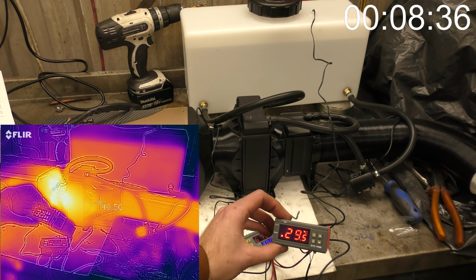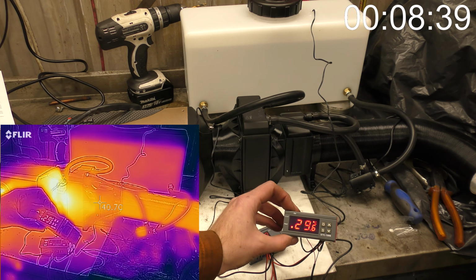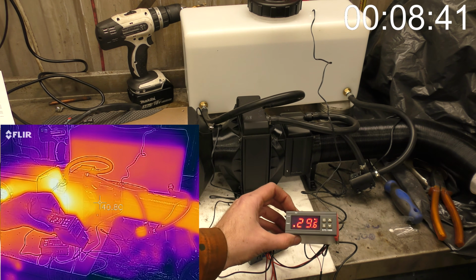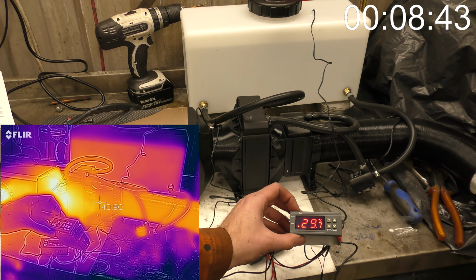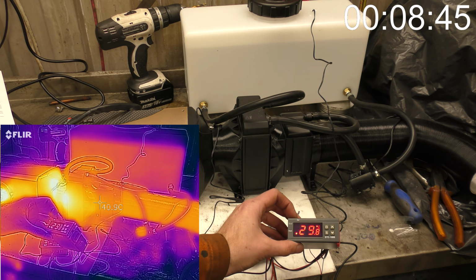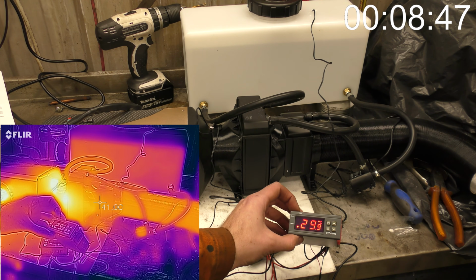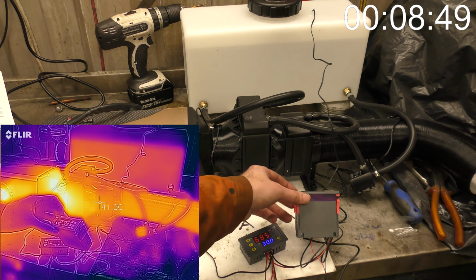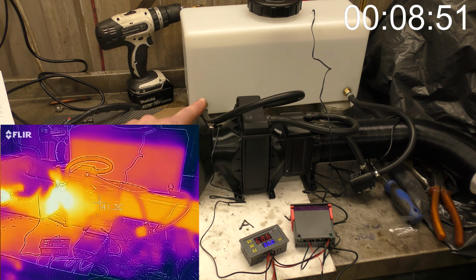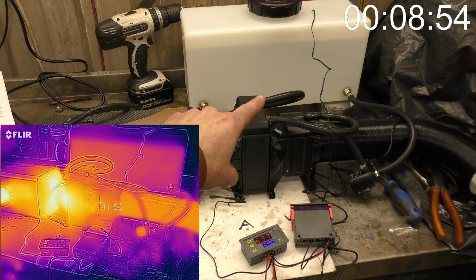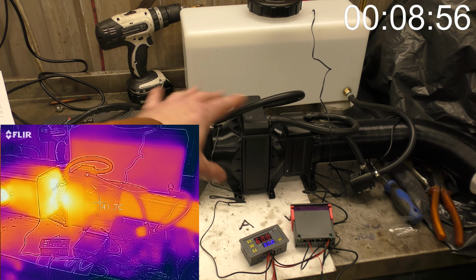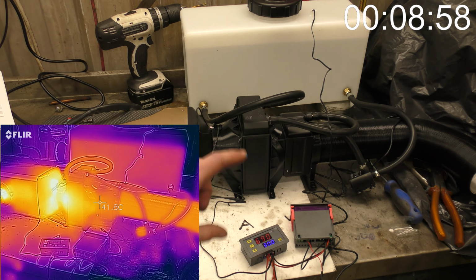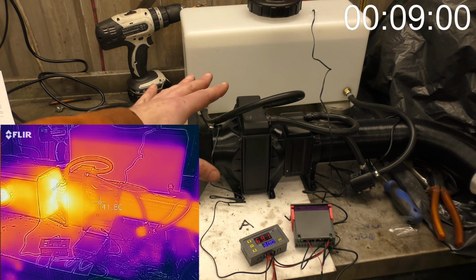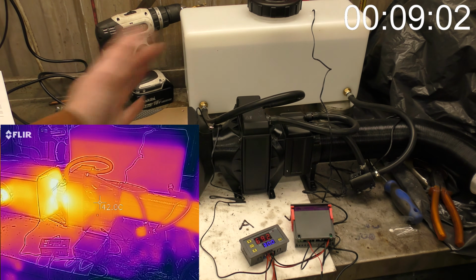That seems more appropriate. You would only want to take it up to 55 if you were trying to sterilise the water, or 65 if you're keeping the same water in a tank for a long period of time. If you're just heating this up to wash dishes, or to empty it in the sink, that's fine. Or if you're using it in the shower, just run your shower till it's empty and you're done, then fill it back up with fresh water.